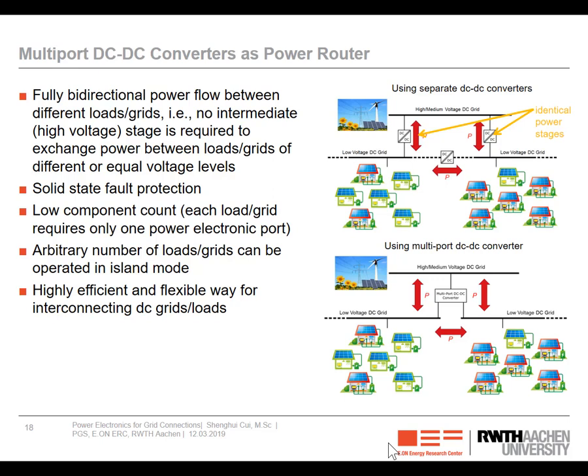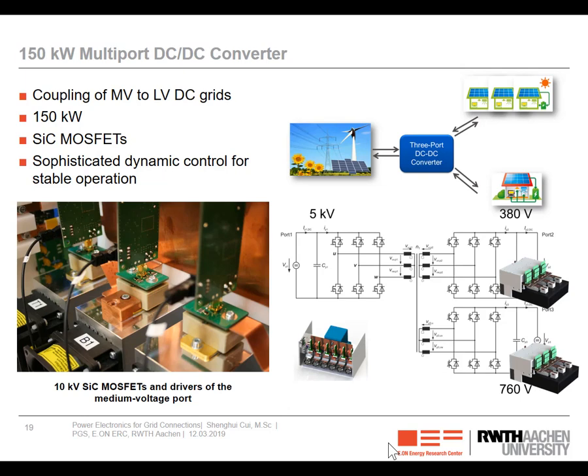This is an idea proposed by Mr. Neubert at our institute. He proposed a so-called multi-port DC converter. So we are able to merge these three converters into one converter, so that the price can be decreased to one half. So here is the circuit. Different from the previous dual active bridge converter, here we have three active bridges, so this converter is called triple active bridges. One bridge will be connected to the 5 kV medium voltage DC grid, currently under construction at our university. And the other two will be connected to one 380 volts low voltage distribution grid and one 760 volts distribution grid. And here we are using two-level converter topologies directly connected to the 5 kV. So we need power semiconductor devices with a very high voltage rating.